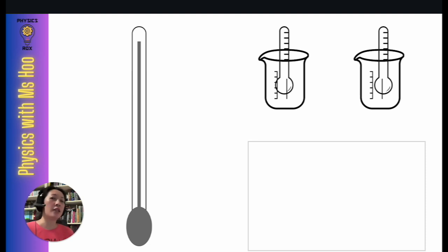But if we have just built a measuring instrument, there may be no scale on it. For example, if we were to build a mercury thermometer, we could build it with all the necessary components. You could have the bulb with the mercury inside, the capillary tube that lies inside the glass tube, and the capillary tube is hollow, allowing the mercury to expand and contract within it. The construction is there, but the scale is not. So this is an uncalibrated thermometer because there is no scale.